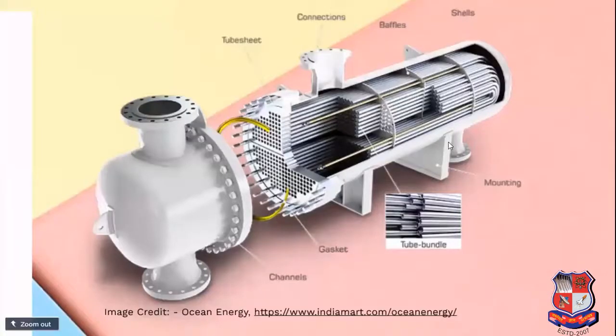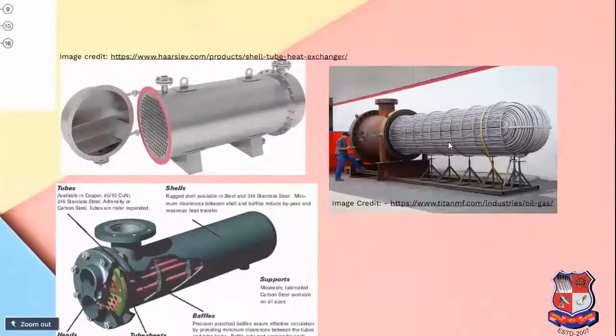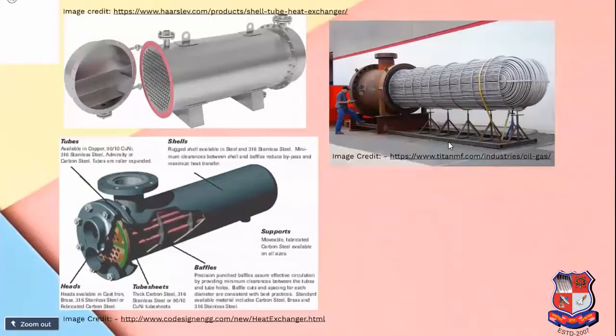Now we will move on to some other examples. These are some industrial examples. You can see in the head how the pass partitions are created, and this is again a similar shell and tube heat exchanger. On the right hand side, this is a Titan manufacturer's U-tube shell and tube heat exchanger. You can clearly see how the tubes are U-shaped, and here you have a Code Design Engineers shell and tube heat exchanger, where you can see the different parts of a heat exchanger and even the different types of head.